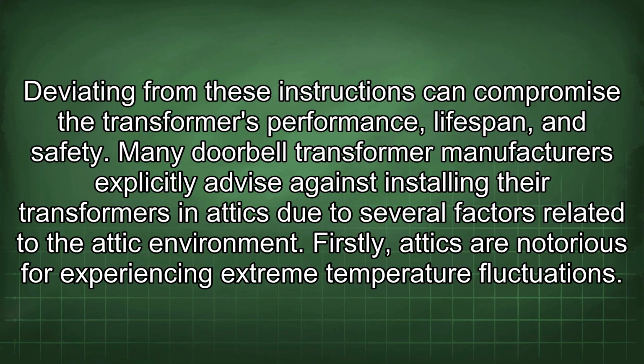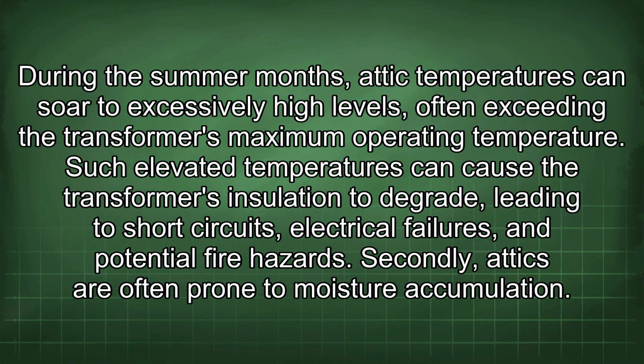Many Doorbell transformer manufacturers explicitly advise against installing their transformers in attics due to several factors related to the attic environment. Firstly, attics are notorious for experiencing extreme temperature fluctuations. During the summer months, attic temperatures can soar to excessively high levels, often exceeding the transformer's maximum operating temperature. Such elevated temperatures can cause the transformer's insulation to degrade, leading to short circuits, electrical failures, and potential fire hazards.